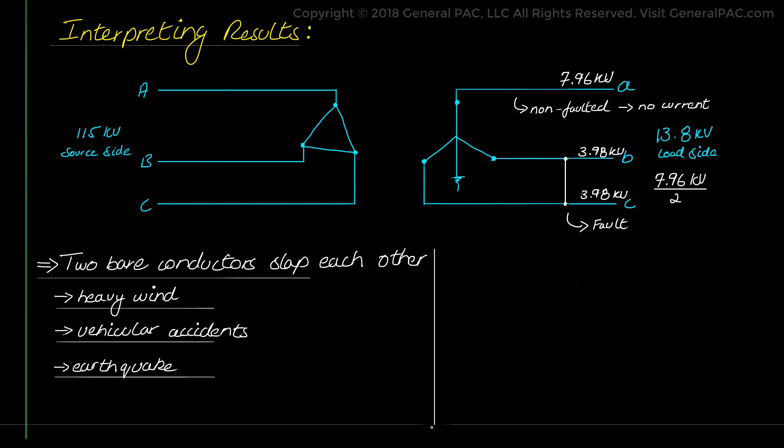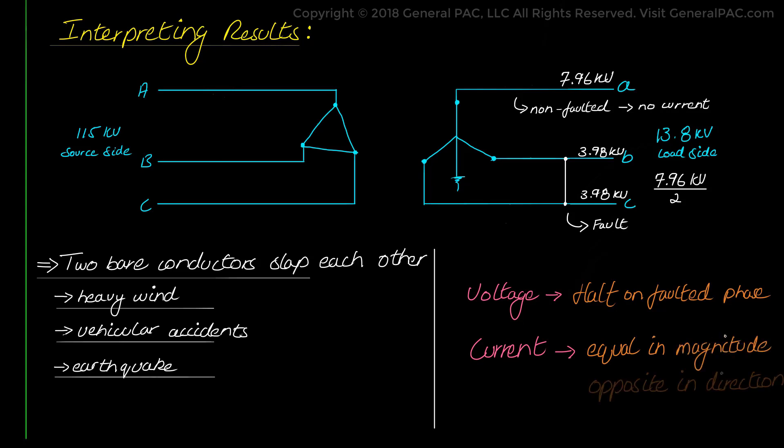When we analyze the fault looking at waveforms, we would expect typically for the voltages to be exactly half for the faulted phase, and the fault currents on the faulted phases to be equal in magnitude but opposite in direction.